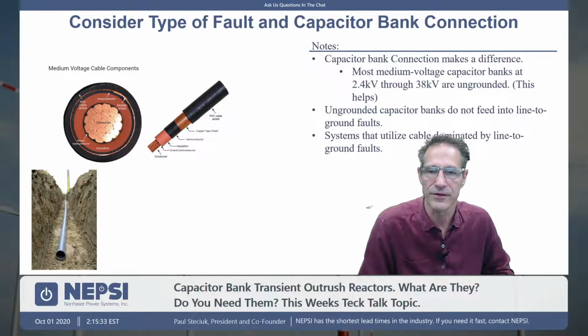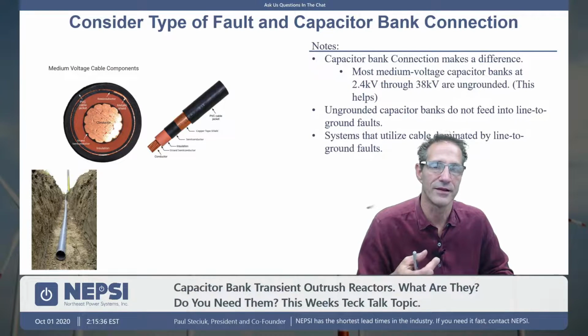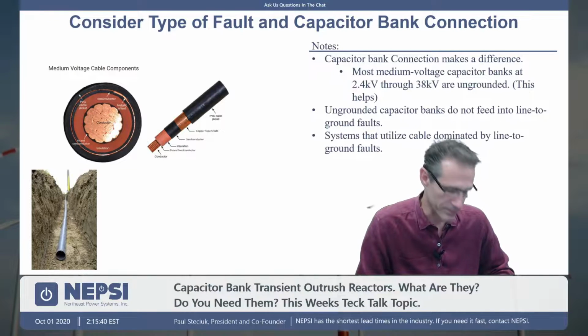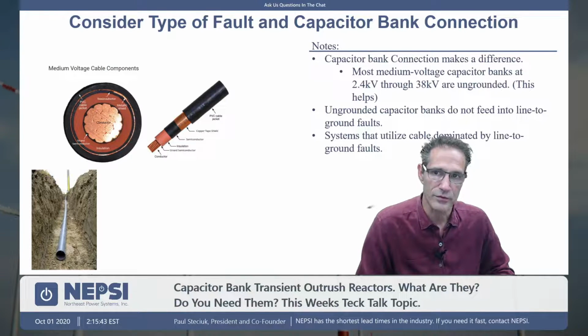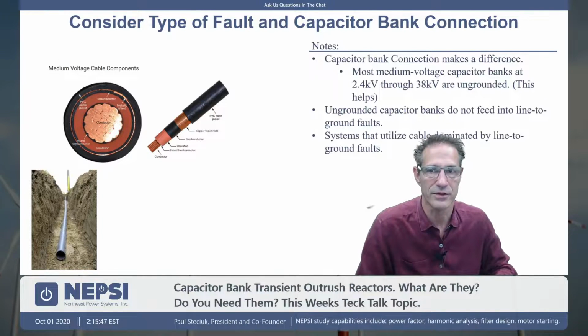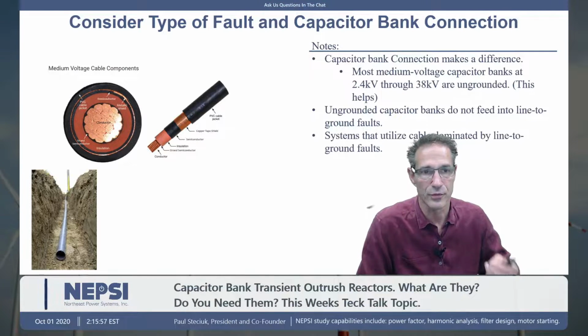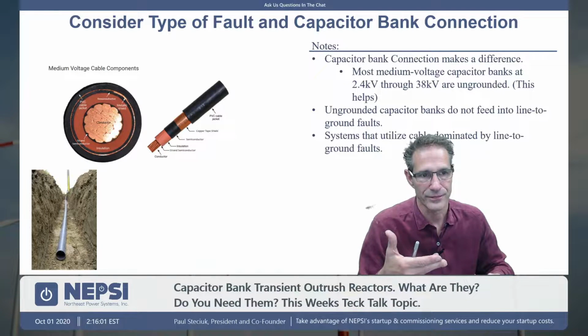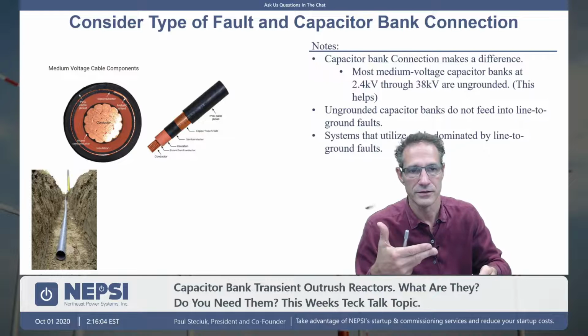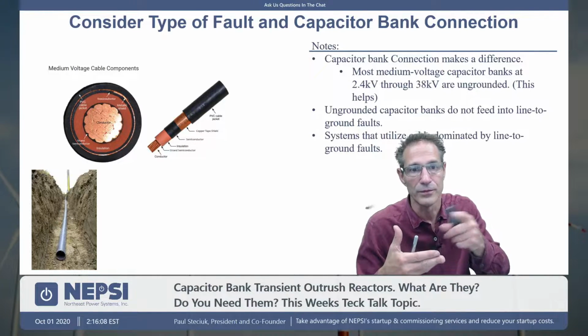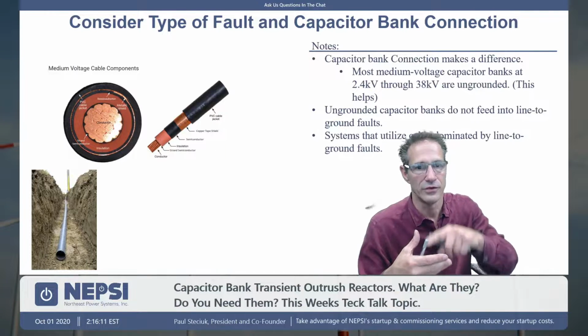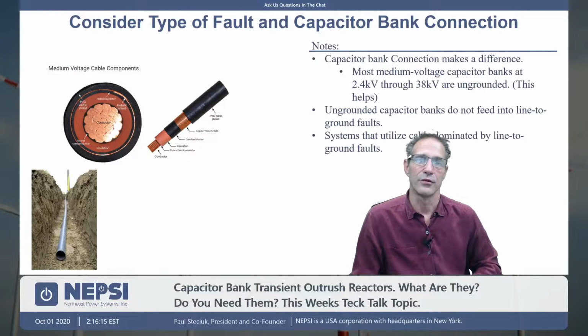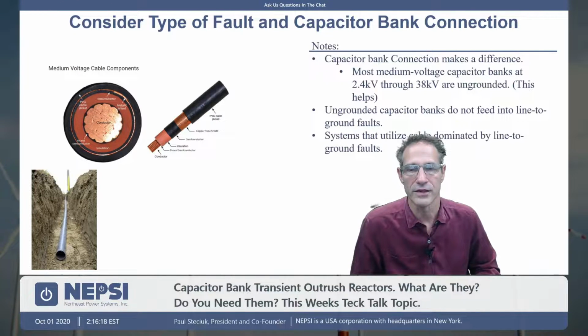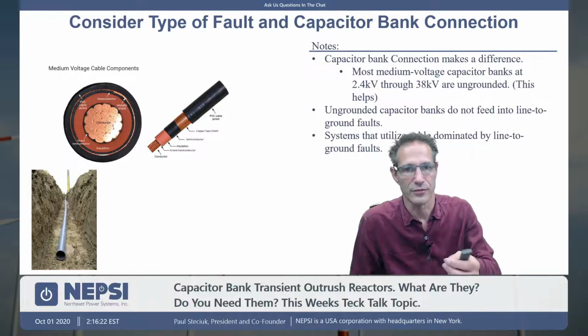So the other thing you have to think about is the type of fault, the type of fault in the capacitor bank connection. And the first thing to realize is that metal enclosed capacitor banks, actually all medium voltage cap banks, are typically left ungrounded, which means that if I have a line to ground fault somewhere out in the feeder, and the cap bank is ungrounded, and I fault, say, a single phase cable, I will not get current flow. The loop is not completed because the neutral of the cap bank is ungrounded. You can't draw a loop around that whole circuit, so therefore there will be no current flow for an ungrounded cap bank into a grounded fault condition somewhere outside the substation.